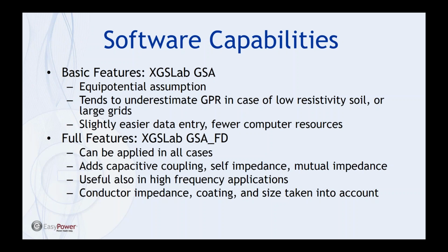Studies have shown generally that the mutual coupling, the mutual impedance, is important, because studies have shown that neglecting it can introduce an error of about 20% into some models. GSA-FD does have this, but it's important to note that some of the competitor products don't take mutual coupling into account until stepping up into another level in the software model, module complexity and cost.